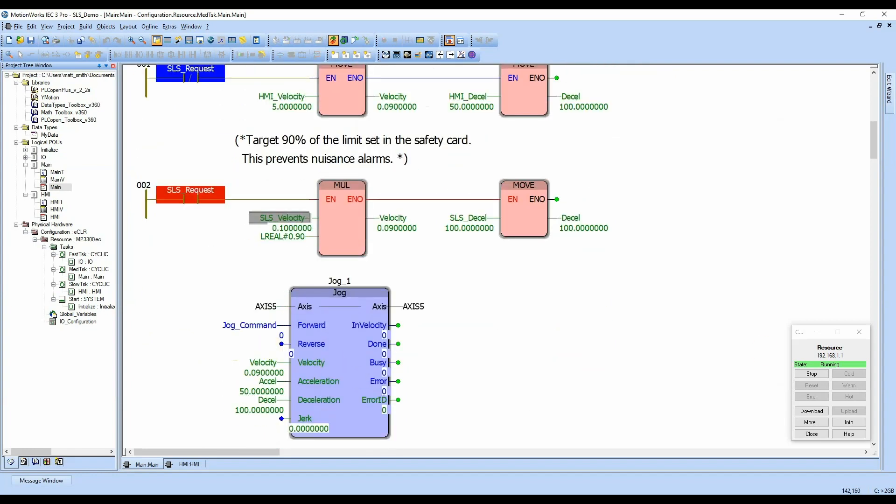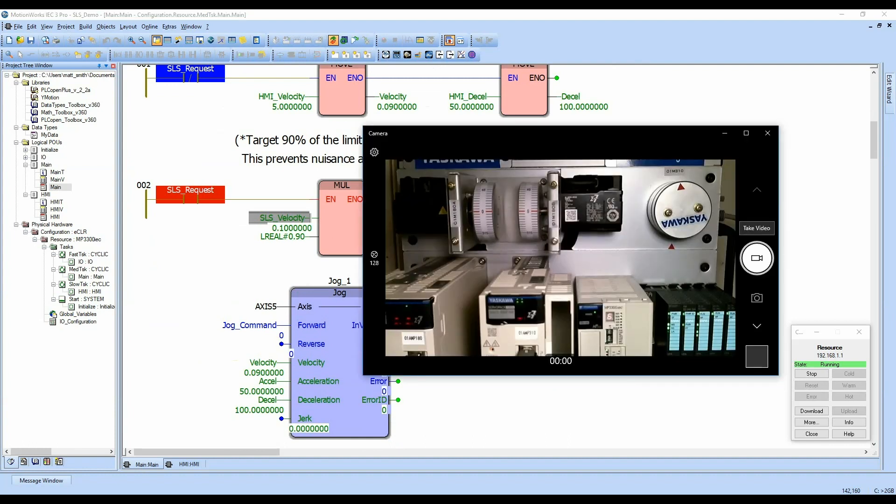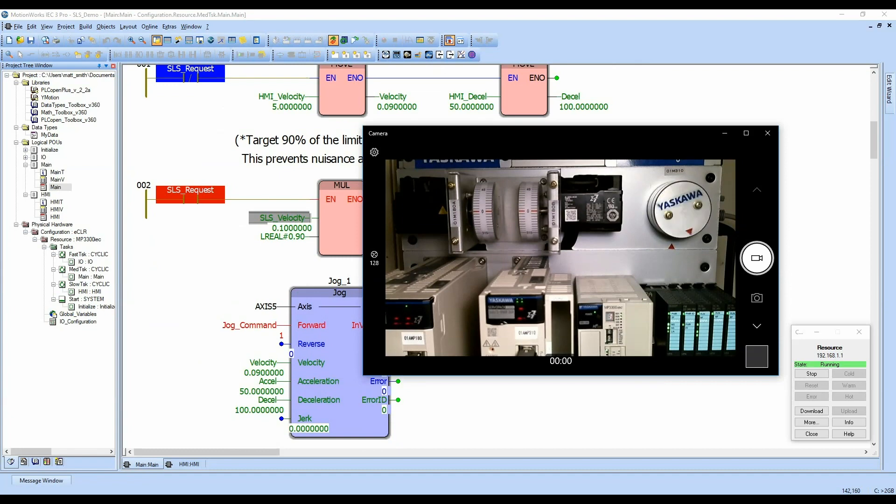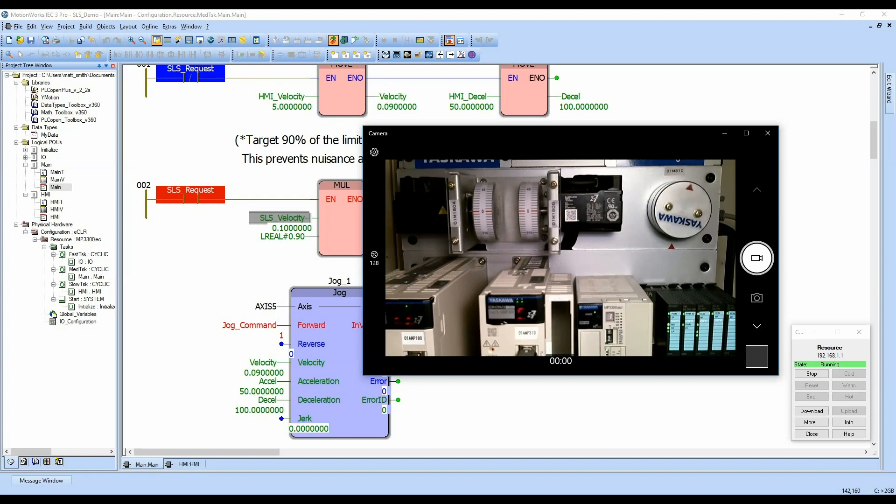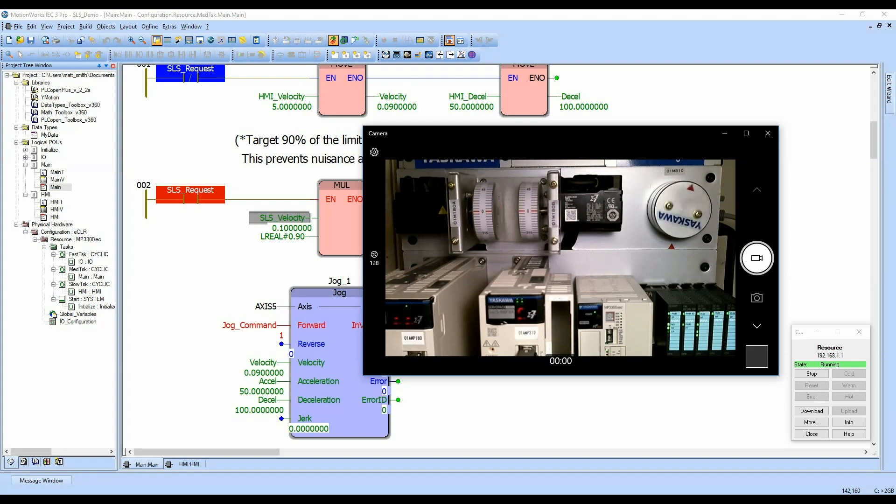And then when we run that, our controller is running the motor at a much slower level. So when we actually give the input into the safety option card, you'll see a little flashing light there on the servo pack. And then once that's solid, that's those time delays that we'd set up before. It's saying, okay, those have passed now and you need to be below a certain value. So as long as you're commanding the motor at a velocity or speed that is below the parameter you set in the servo pack, then it can operate as normal. If it exceeds that, then it's going to disable the axis.